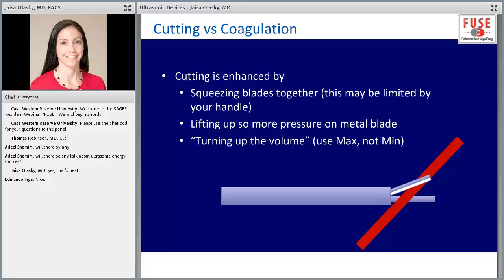To get into a little bit more detail about how this device works, as I mentioned, there are two different ways that the cutting works. The first one is by squeezing the blades together, you'll be cutting the tissue. Unlike the bipolar instruments that we just heard about, where lifting up is not a good idea, with the ultrasound devices you do actually want to lift up if you're trying to cut. You can lift the instrument up, but you can also have an assistant grab the tissue so that you're having more tension on the tissue and more pressure on that blade. So that's one of the ways you cut. This is usually on the max setting, and you can actually adjust what's called the blade excursion, which is the amplitude of the blade oscillations themselves, in order to change the effects of this.